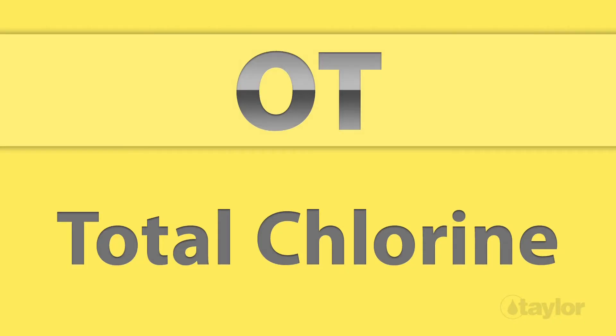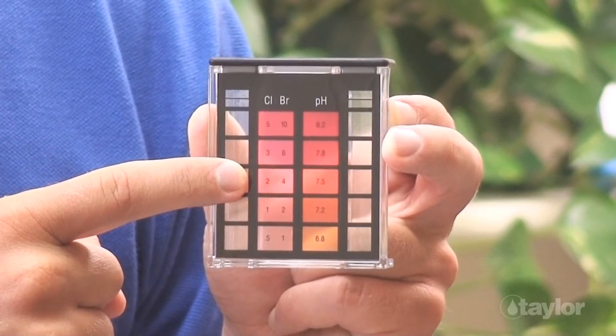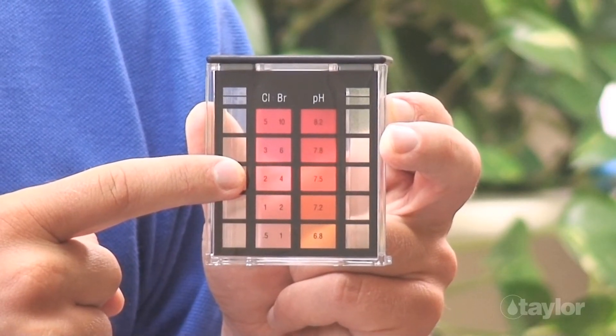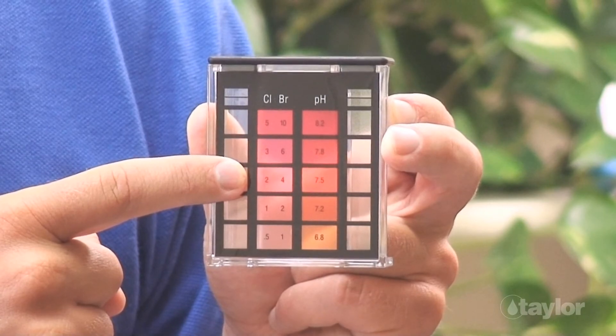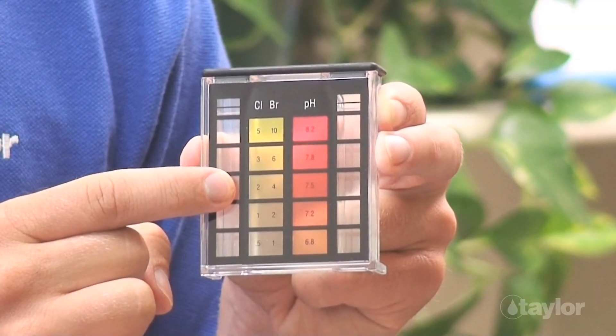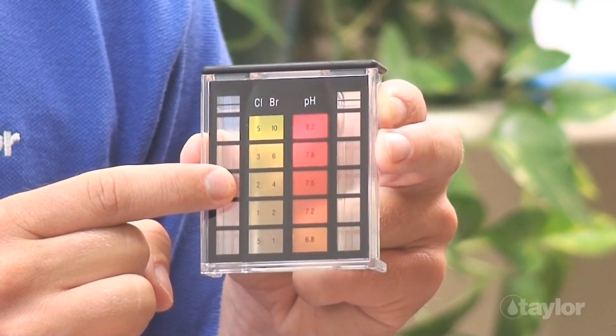DPD can distinguish between the free and combined forms of chlorine, while OT can only read total chlorine. A quick way to tell if a test kit employs the DPD method is to look at the color standards in the test block. If they are shades of pink, it's a DPD test. If they are shades of yellow, it's an OT test.